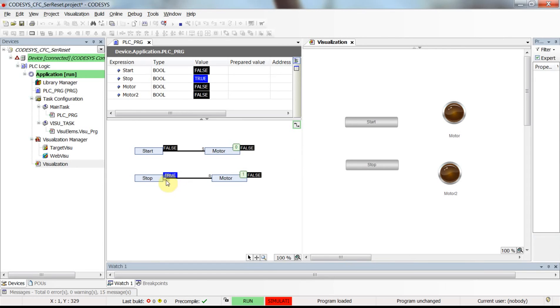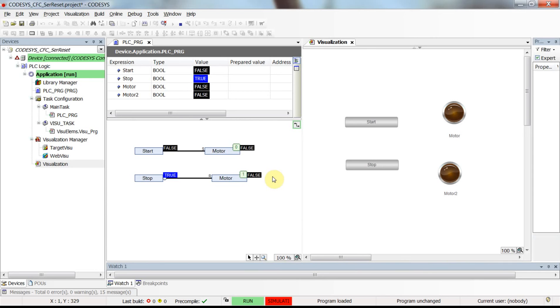One more important thing: you can see markers 0 and 1 here, which indicate the execution order in CFC. Unlike ladder logic which has networks or rungs, or structured text which executes line by line top to bottom, in CFC we need to explicitly determine the execution order using these numeric indicators. In this case instruction 0 executes first, then instruction 1.